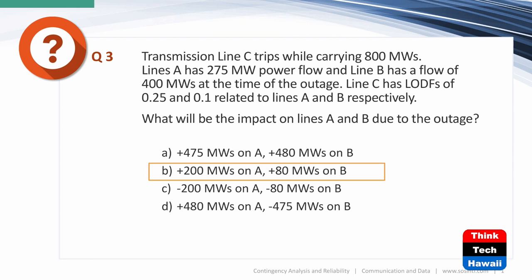When you have three parallel lines and lose one, the flow still has to get from source to load and will find its way through the remaining lines and potentially out through other lines in the interconnected system. So flow increases — in this case from 275 to 475 on line A, and an increase of 80 MW from 400 to 480 on line B. The question asks for the impact, which is 200 and 80 megawatts.